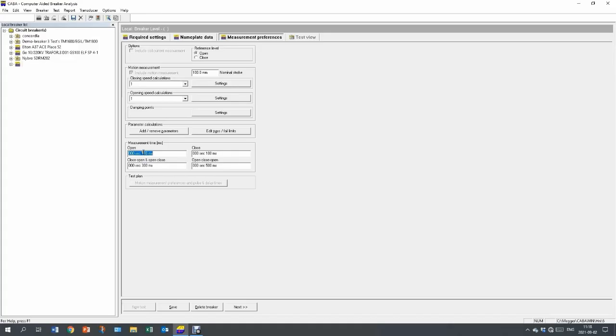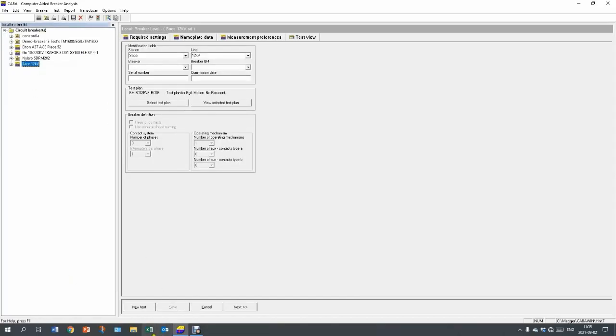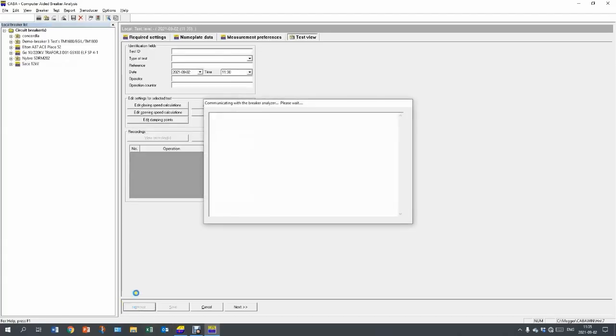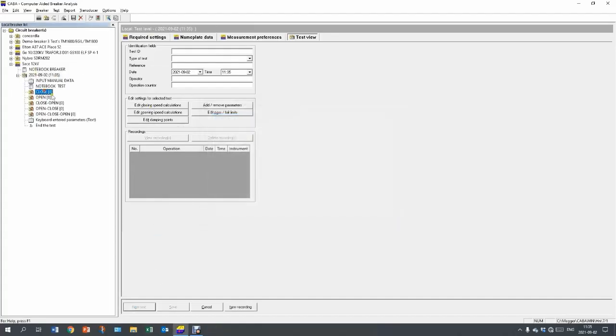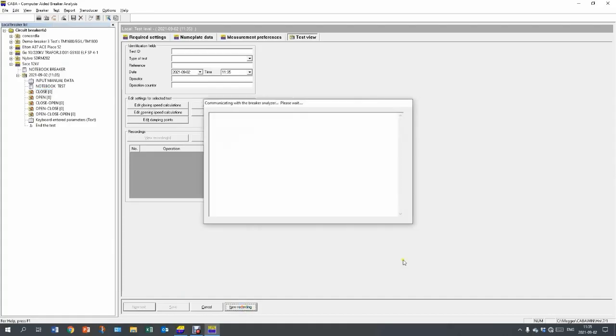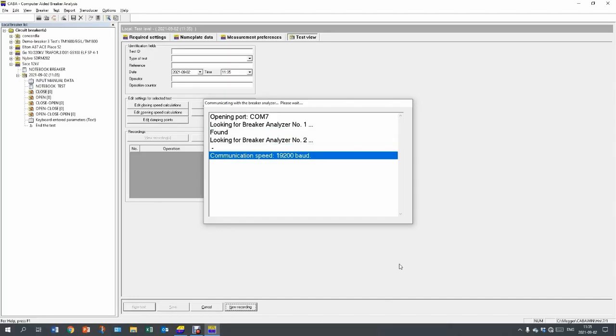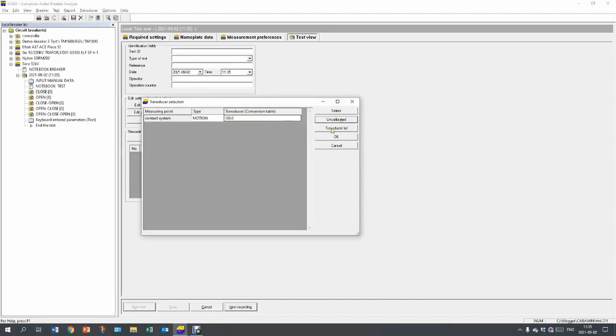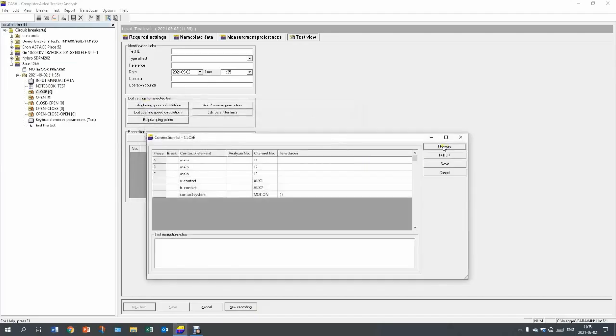I extend the measurement time on both close and open operation. I know this breaker is slow and I need enough time to catch the whole motion, not only the timing. I save, and now I have my new object in the list. I continue with creating a new test, and start with a close operation. I push new recording, and select uncalibrated transducer and OK. I push measure and will continue with controlling the breaker from the analyzer.